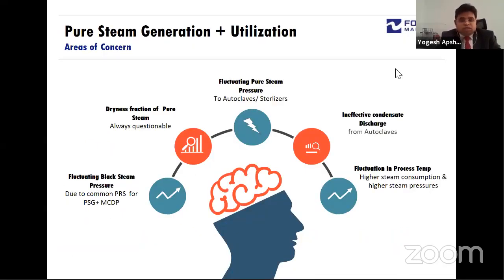So as far as pure steam generation is concerned, what are the typical areas of concern? What we have seen is a common PRS for the pure steam generator and the WFI still. The dryness fraction of the pure steam is always a point of question or a point of debate. There are no systems which can predict or calculate the dryness fraction of the steam. Then there are fluctuating pure steam pressures going to the autoclaves and the sterilizers, ineffective condensate discharge, and fluctuation in the process temperatures as well.